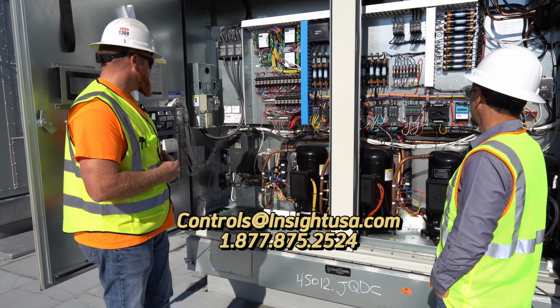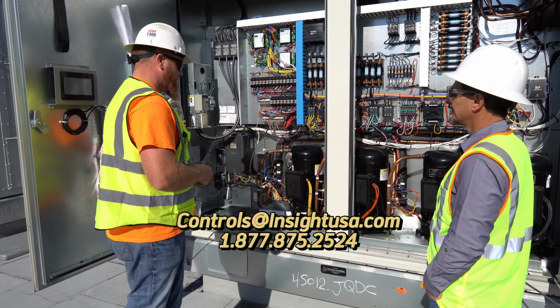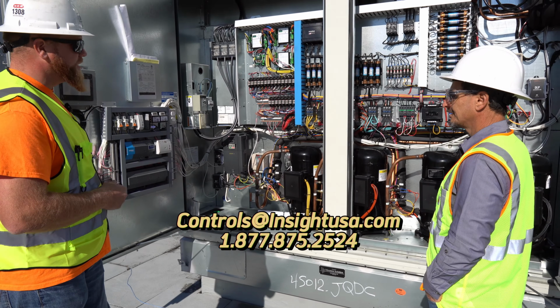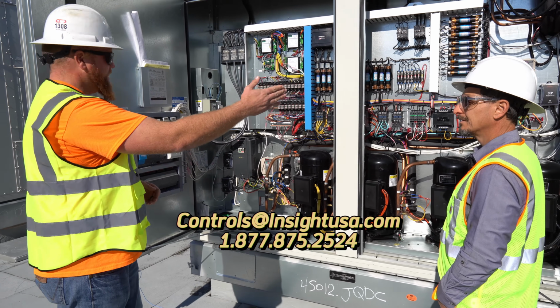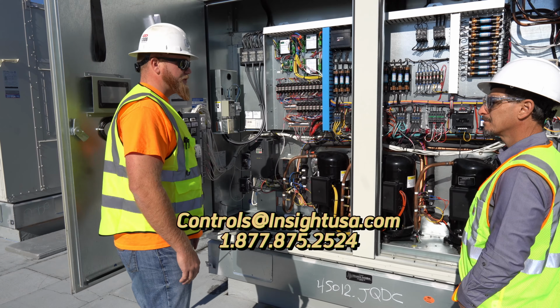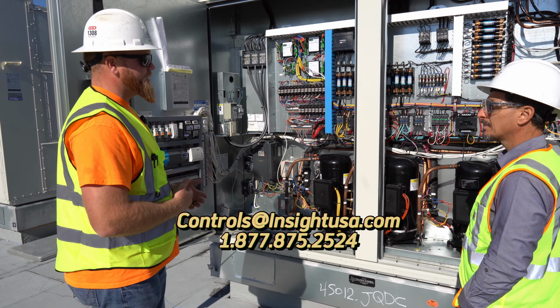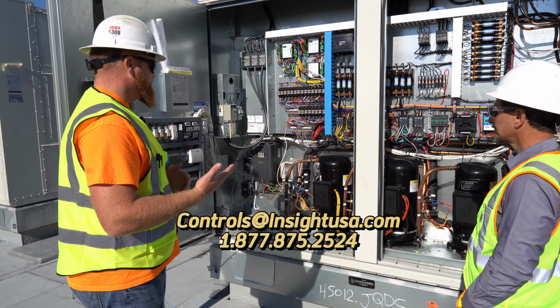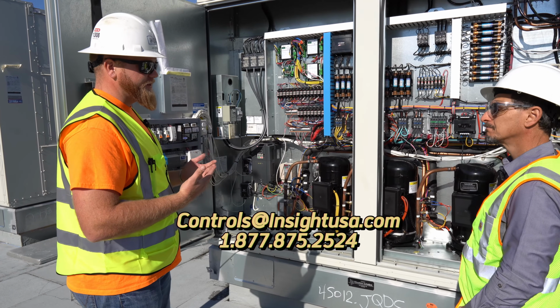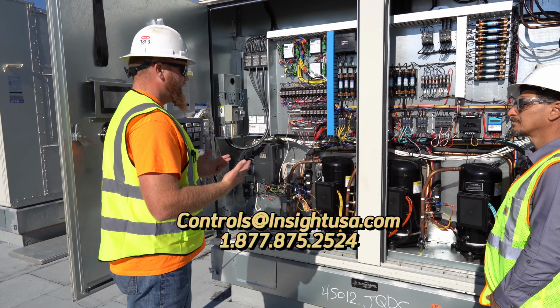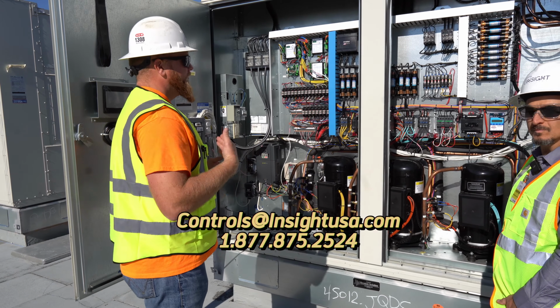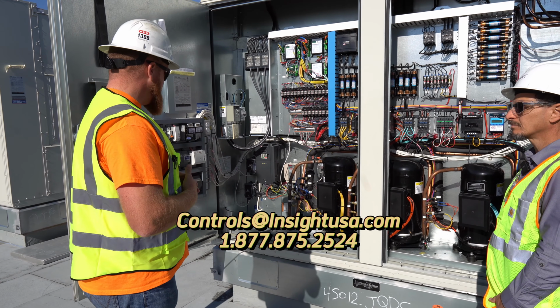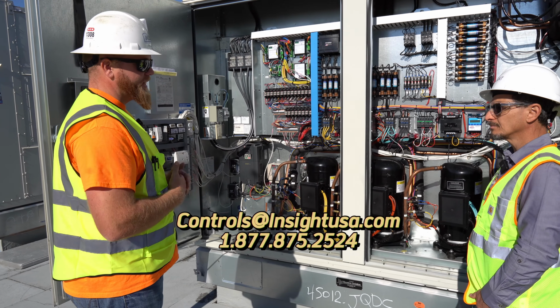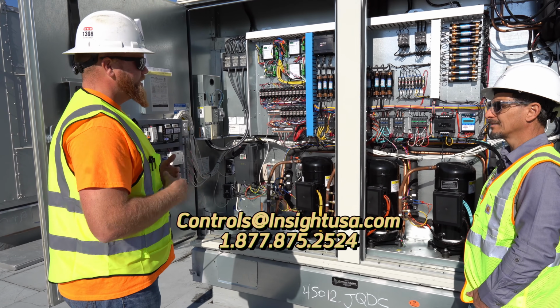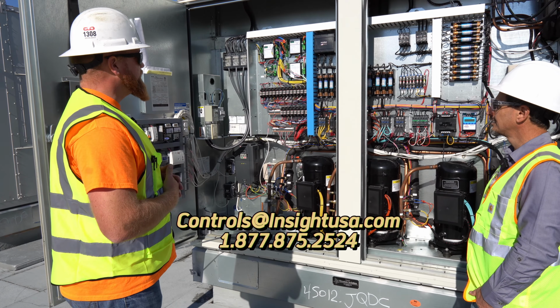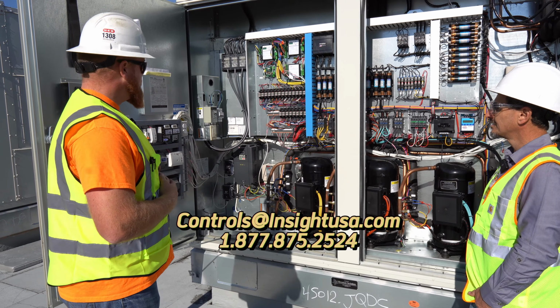blow any ductwork apart. So everything does come back to our inputs, so we can read all of our sensors that are installed. The DLPs that you see here, those are for the filter monitoring, taking the differential pressure from the high and the low side of the filters. You can set an alarm up in a trend to see when it's time to change filters, with different seasonal changes, pollen season, all that kind of stuff. So every 3 months might change to 1 month during a high pollen season. Sometimes in a dry summer, it might change out to 4 months. So you can monitor that differential pressure and be able to know when it's time to change filters.